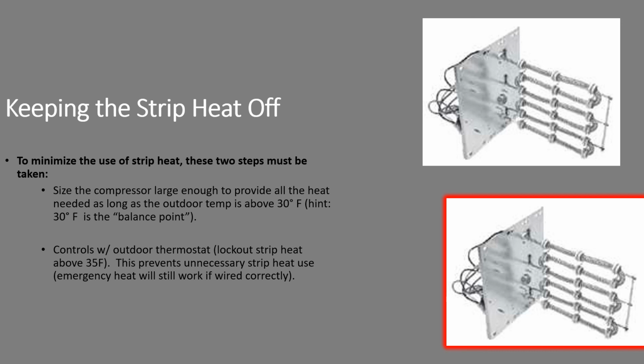In order to do this, we have to size correctly. And notice that we call the lockout of strip heat at 35. That gives you sort of 5 degrees of flexibility, if you will. If you size for 30 and keep the strip heat off at 35, you'll avoid unwanted customer complaints.